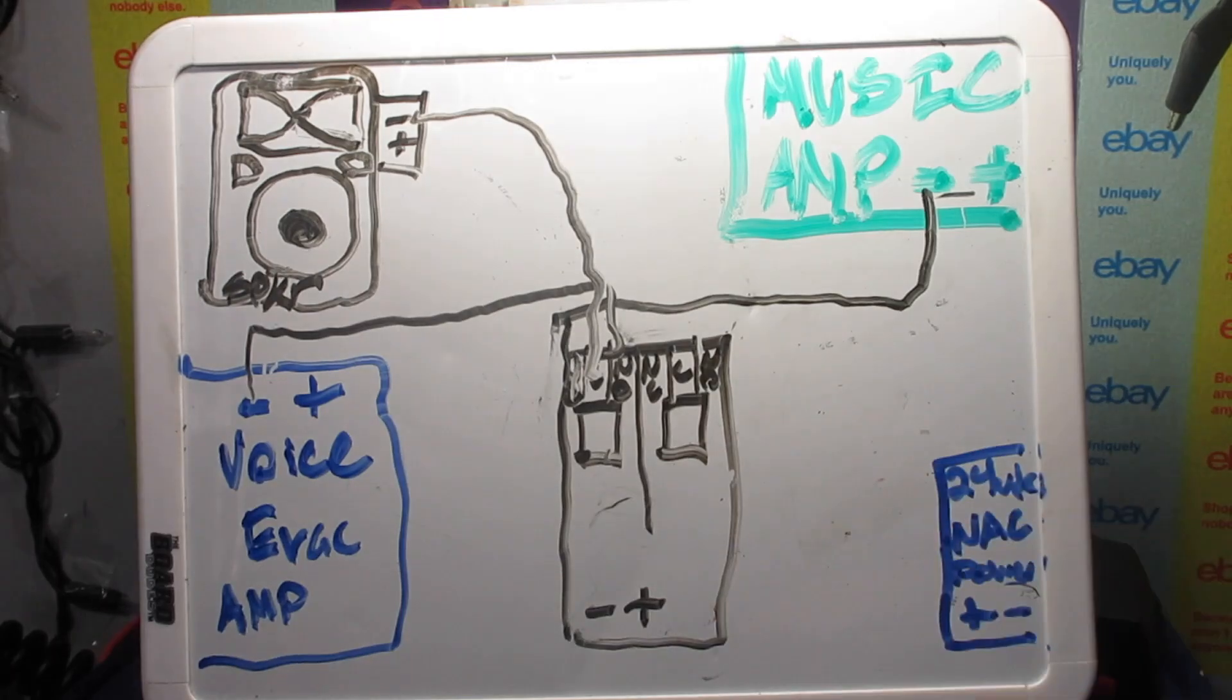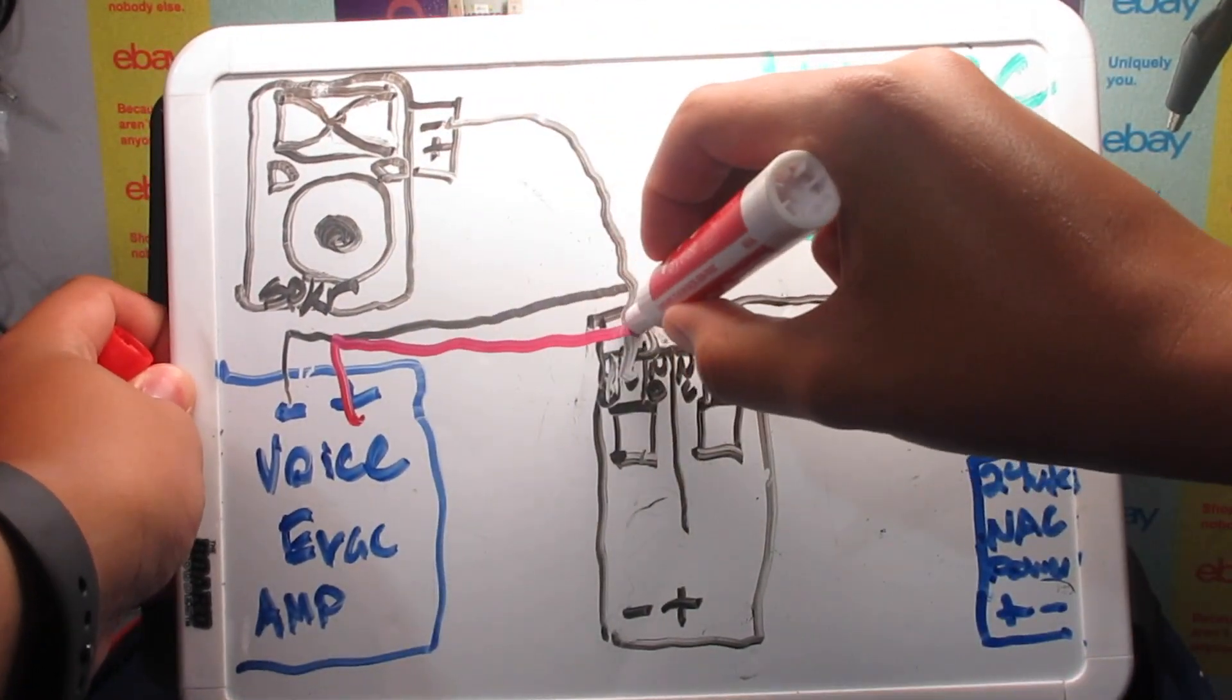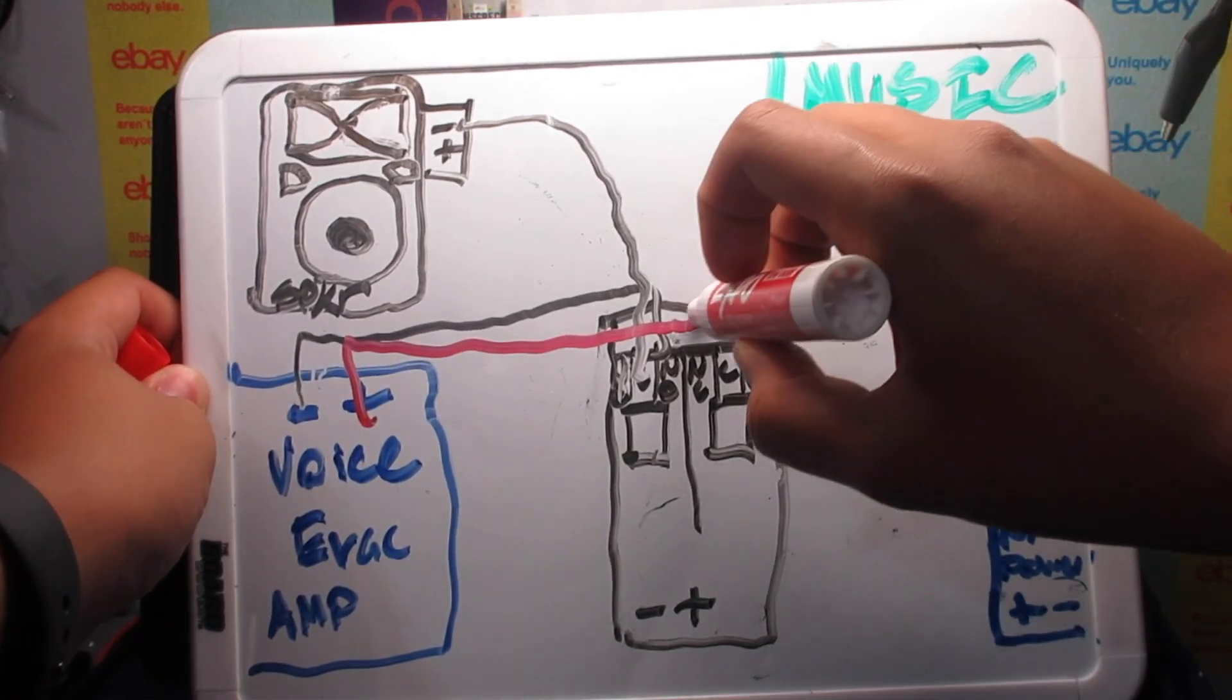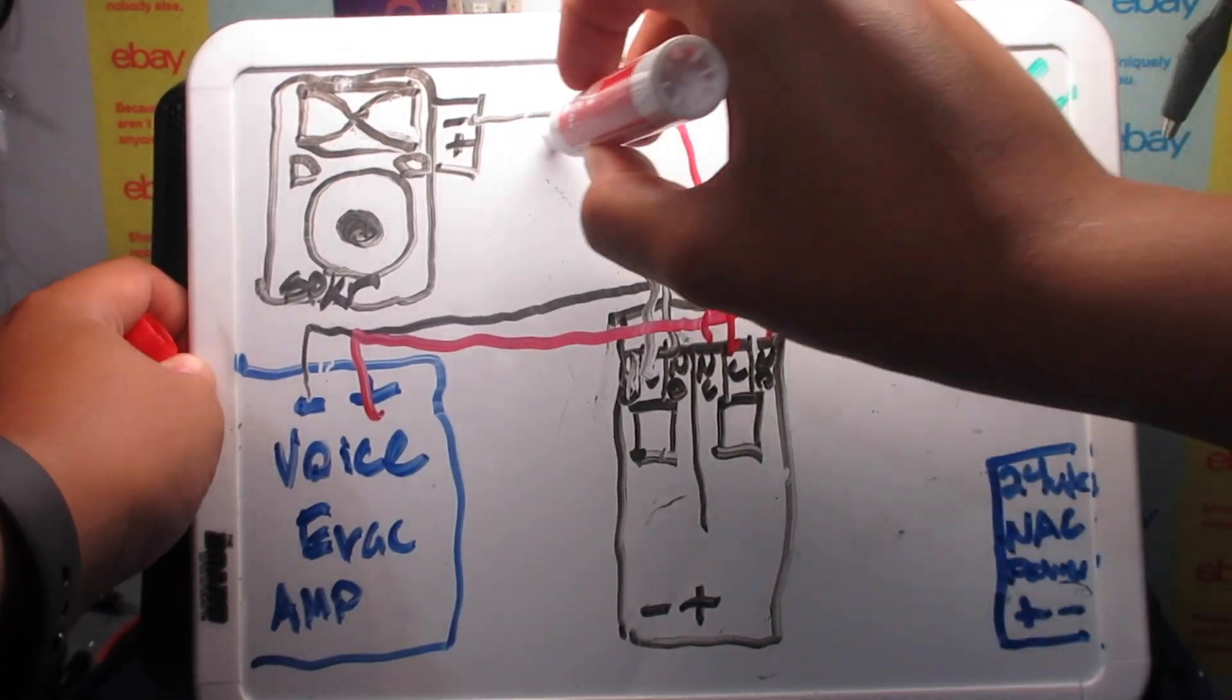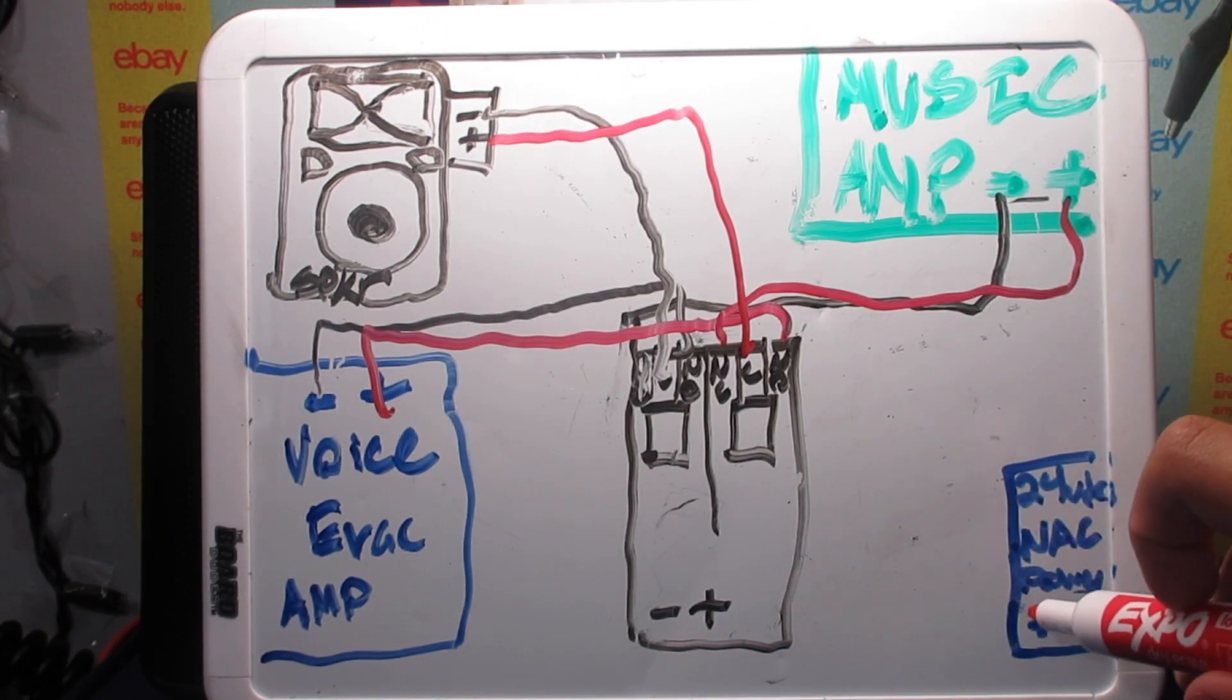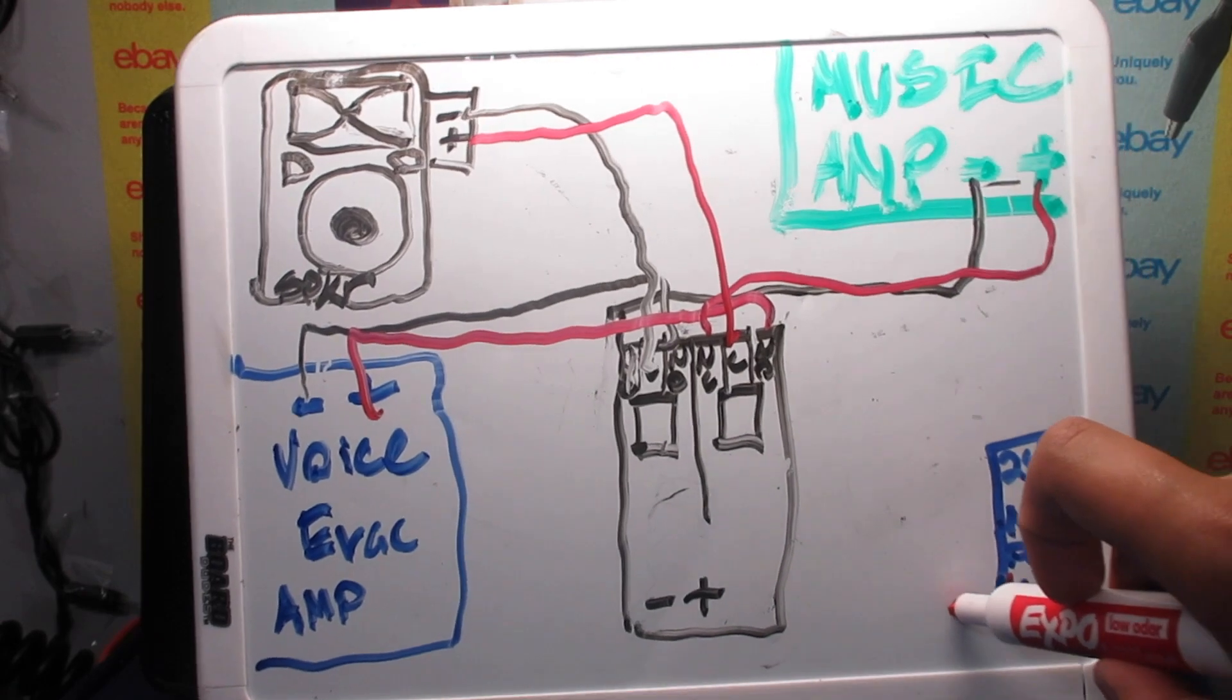So then we're going to do the same thing with our positives. Take our voice evac and put it onto the normally open, take our amp, put it onto the normally closed, and take the common and put it onto the speaker. Now what we need to do is hook it up to our alarm panel, which will be a notification appliance circuit or some sort of control module.